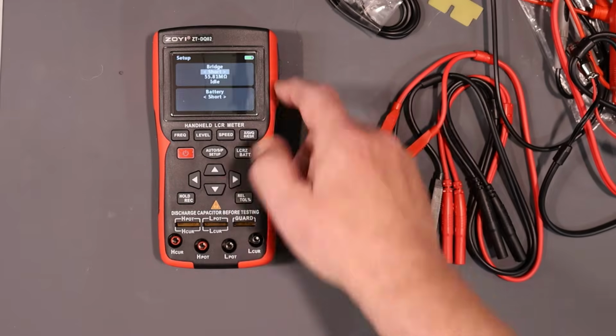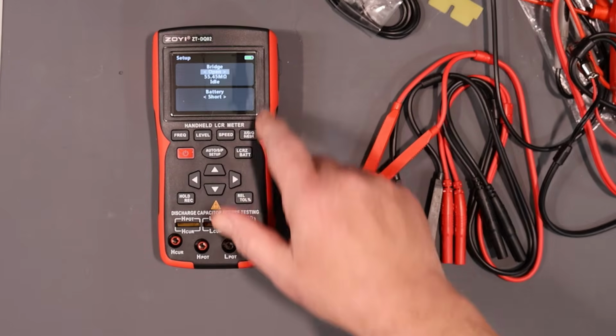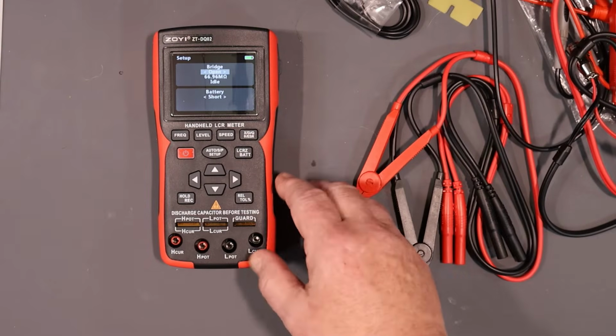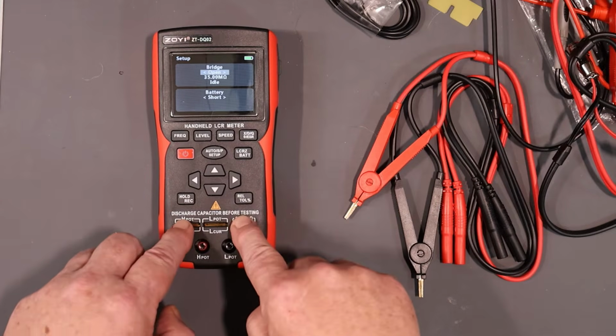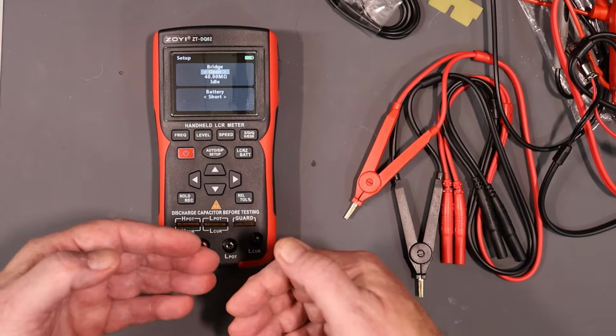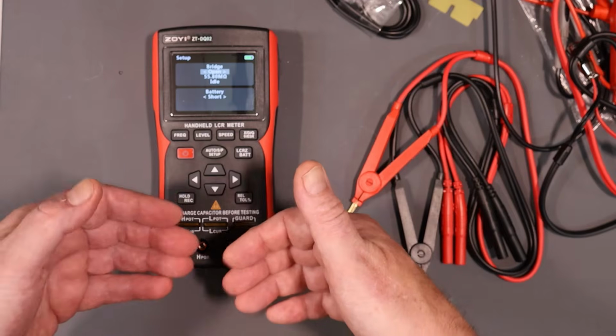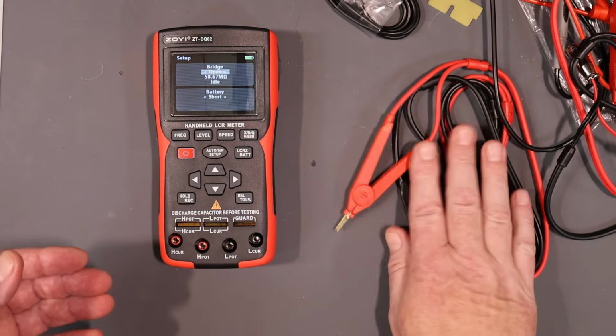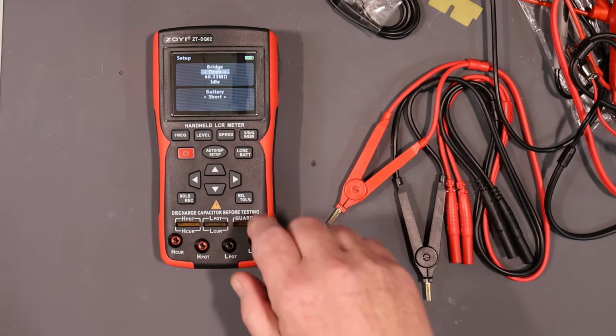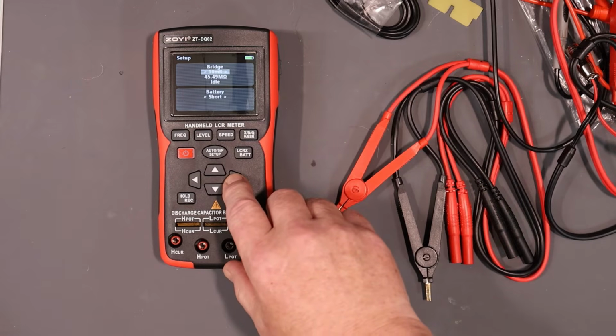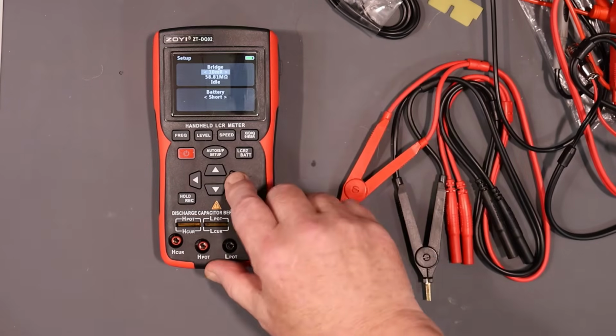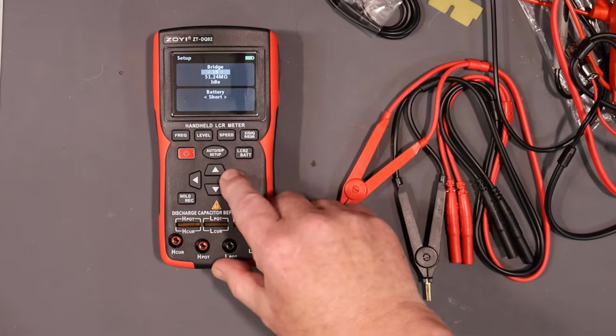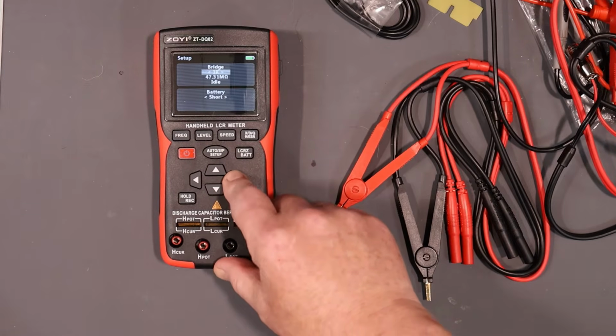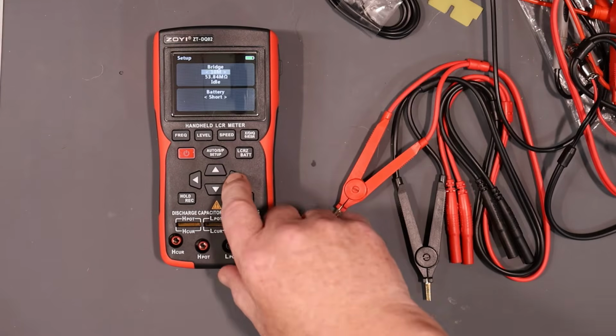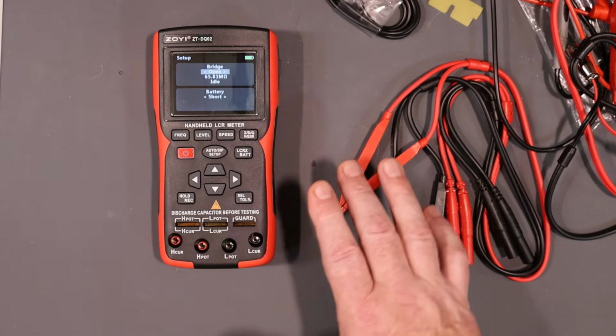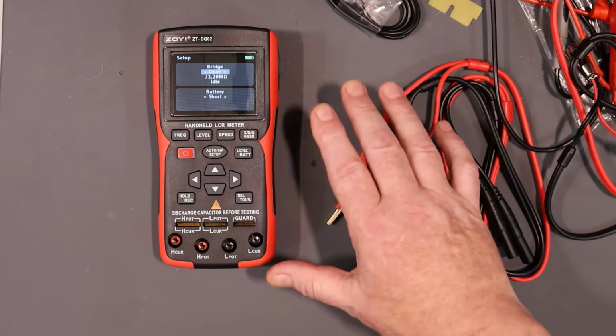If you go in here you can see, so you can do a short calibration and an open calibration, and generally speaking they're the only ones I would do. So if you're moving from using these terminals here to using the 4-wire, you want to do an open and short calibration, and then if you move it back again you do the open and short calibration again, just to take the resistance and the capacitance of the leads out of the equation. And it also allows you to do all these other ones here, so you can calibrate it for 10 milliohms, 100 milliohms, 1 ohm, 10 ohms, 100 ohms, 1K, 10K, 100K, 1 meg, and 10 meg. So that's an awful lot of high precision, low inductance resistors that you're going to need to do that.